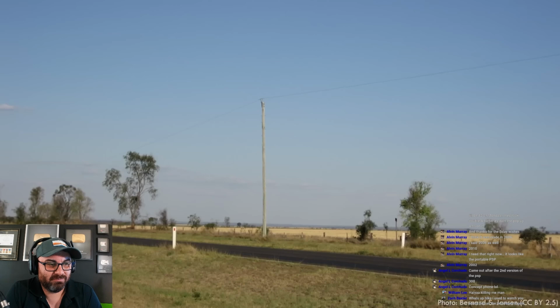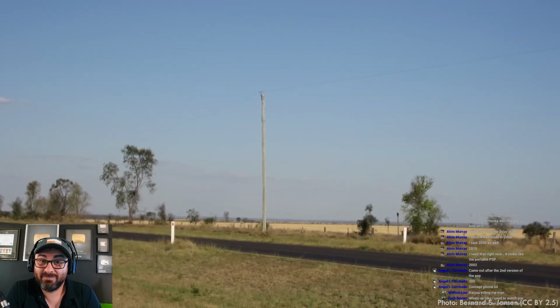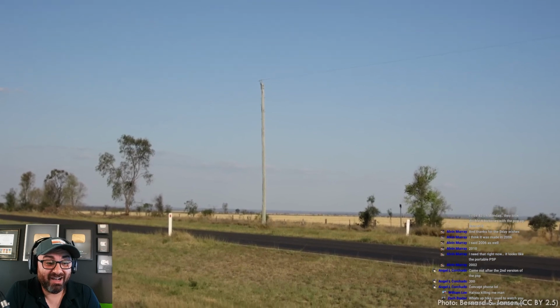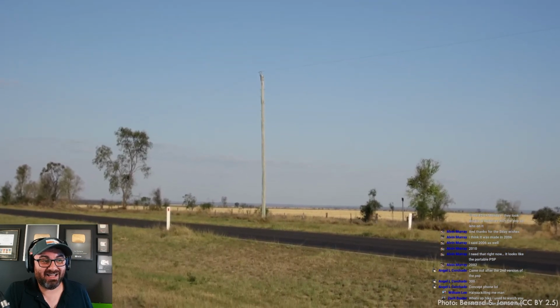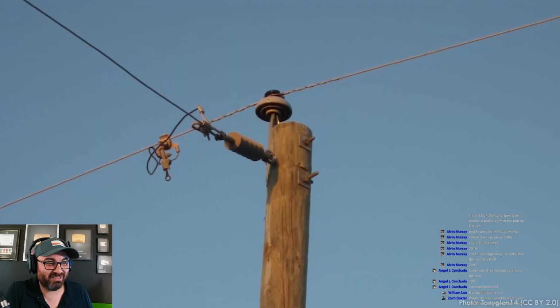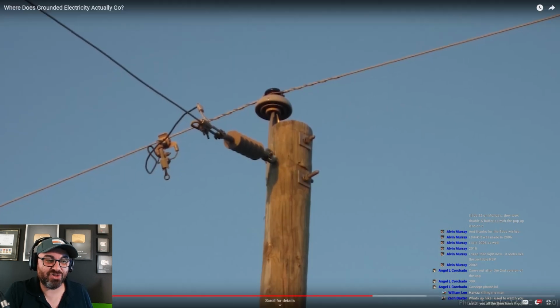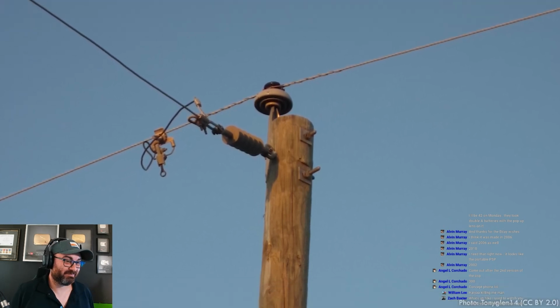But not all power systems use the ground just as a safety measure. There are systems where the earth is actually the primary return path for current to flow. The ground is essentially the neutral line. Electrical distribution systems called single wire earth return, or SWER, are used in a few places around the world to deliver electrical power in rural areas. Using the earth as a return path can save costs since they only have to run a single wire. But of course, there are safety and technical challenges too.